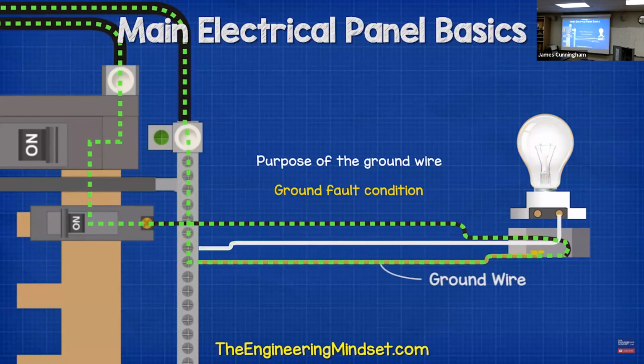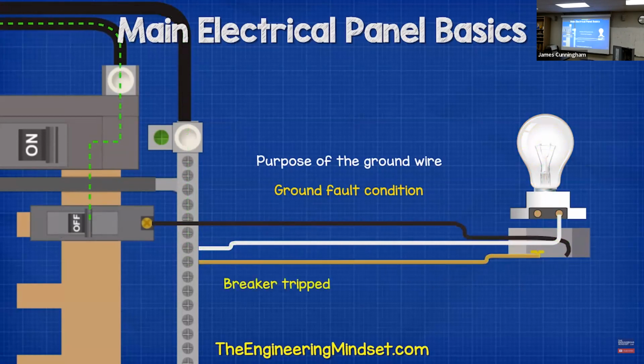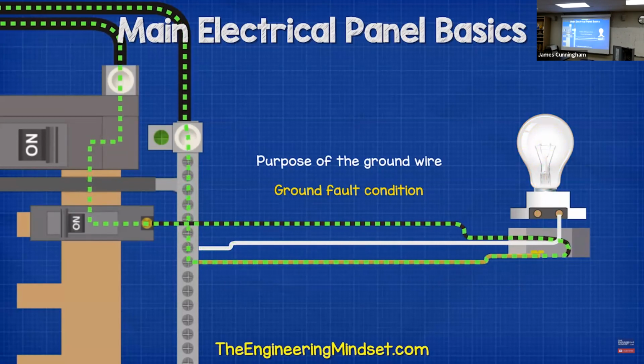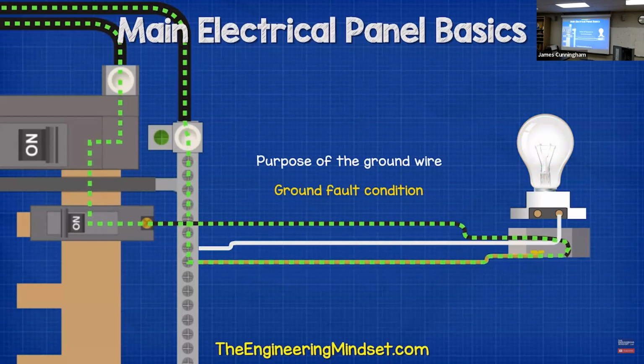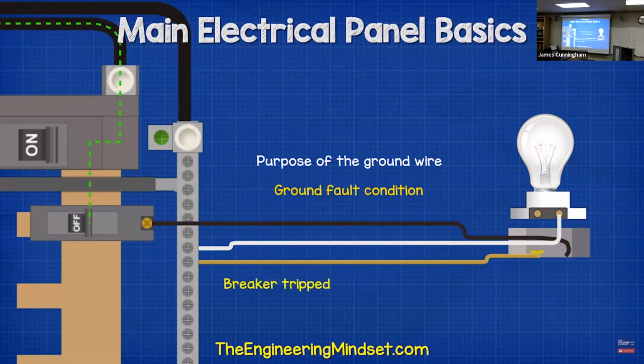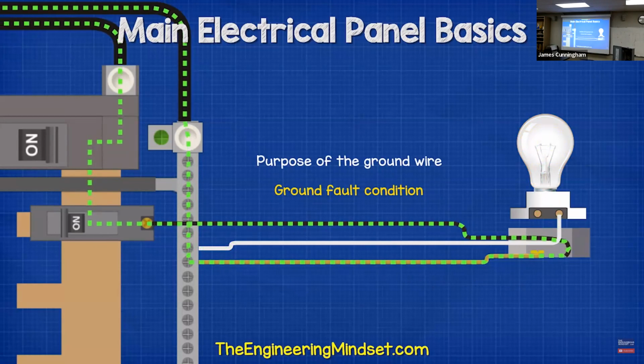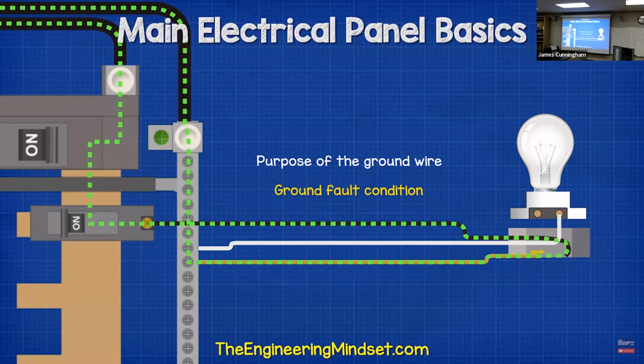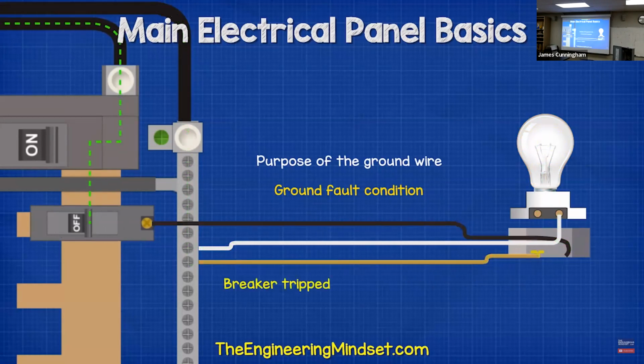If, for example, the hot wire came loose and touched the metal casing of the light fitting, the ground wire provides a low resistance path back to the panel. Without this path, electricity could flow through you if you touch the metal box. As the current flows through the ground wire, it will increase the current and that will trip the breaker automatically.